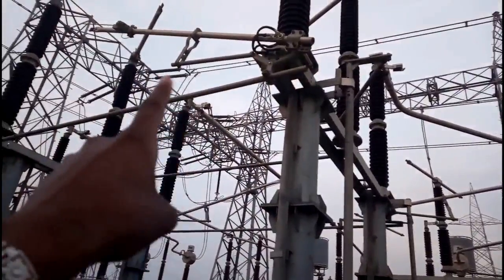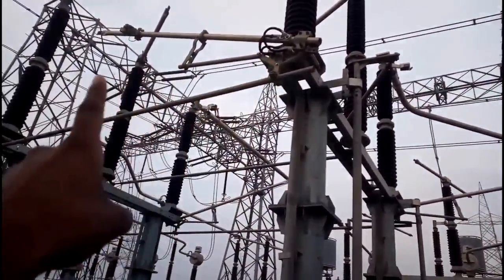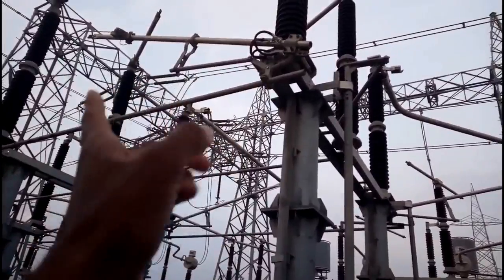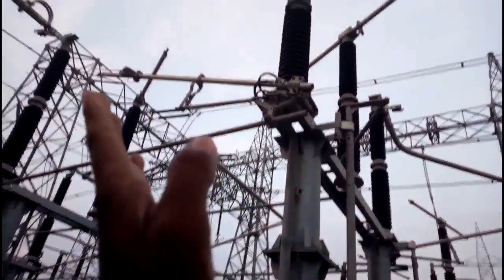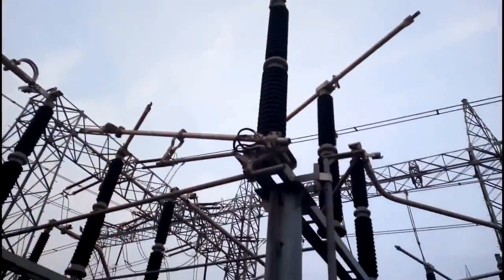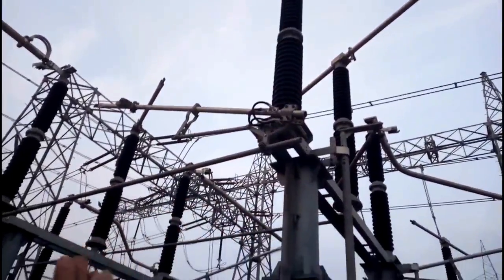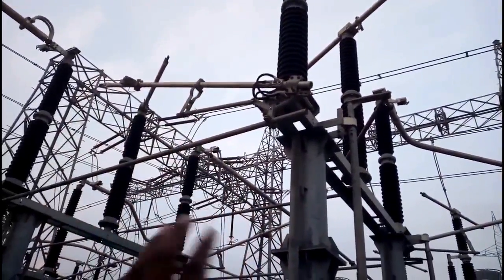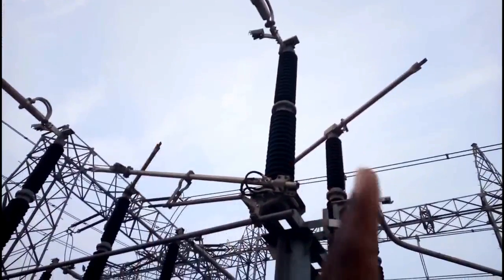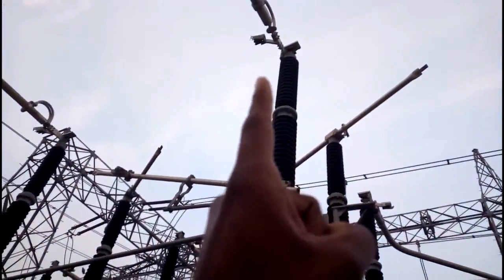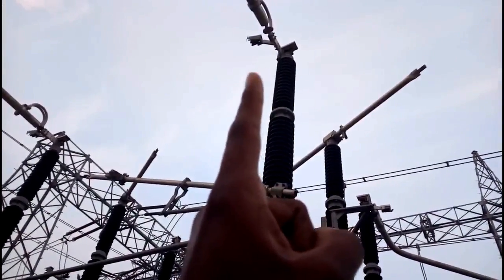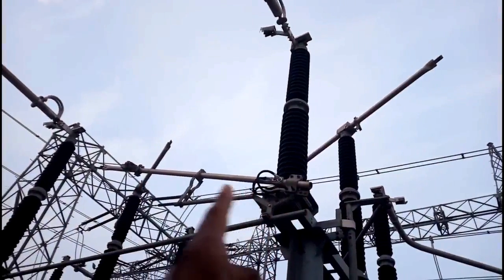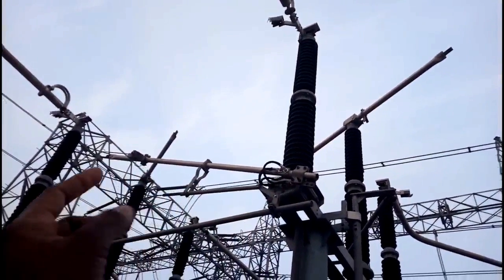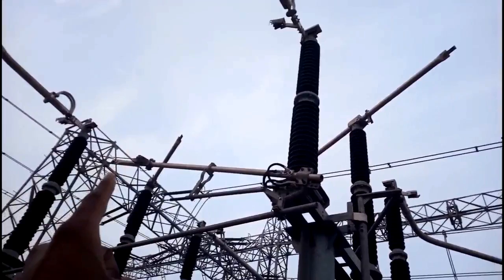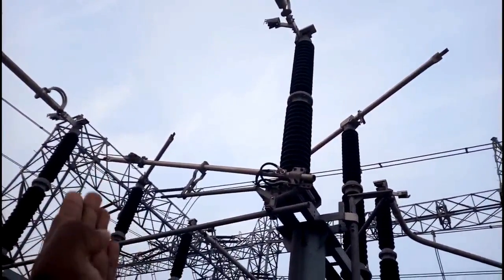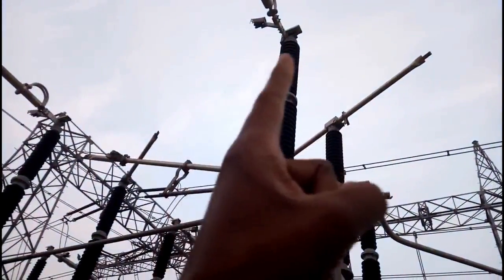This rod is called the earthing switch. It is otherwise called the earthing link, and this earthing rod will be connected there when you close it. Okay, so this earthing switch will be closed only. See, you are looking there, the contacts are there, the female contacts, and here at the top of this earth switch is the male contact. So when this goes there, it will be fixed inside.